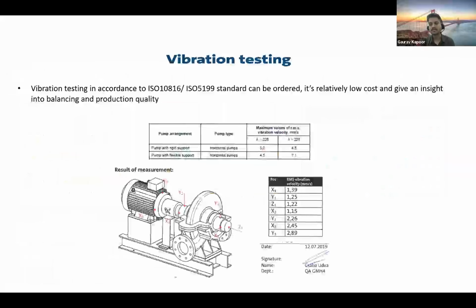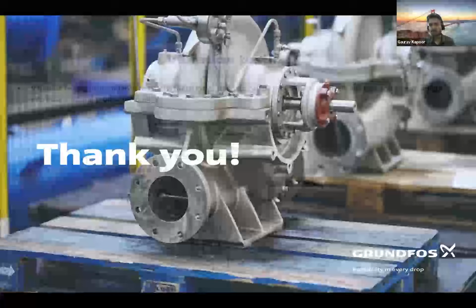And the last test will be vibration testing. It is also very important that the vibration is tested in the factories as per ISO 10816 or ISO 5199, which really makes sure that your machines, your impellers and your shafts are very well balanced while manufacturing, and it gives you again a longer life of the pump and lower maintenance breakdowns, or lower maintenance cost, or lower OPEX. With that, we'll come to the end.